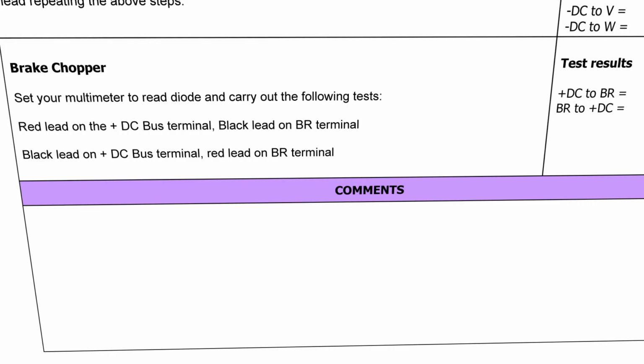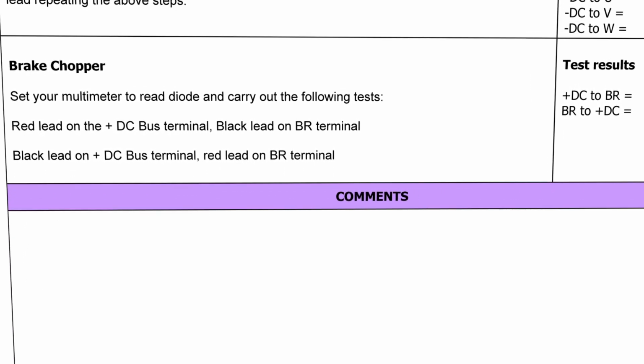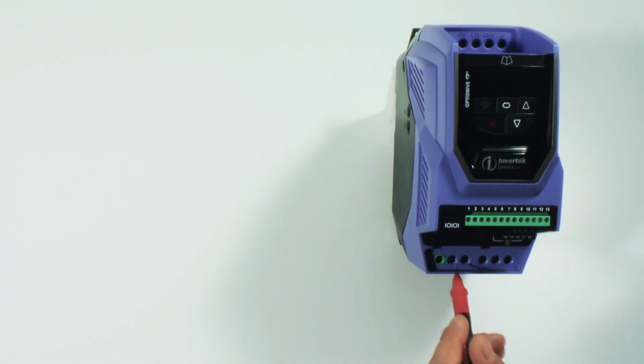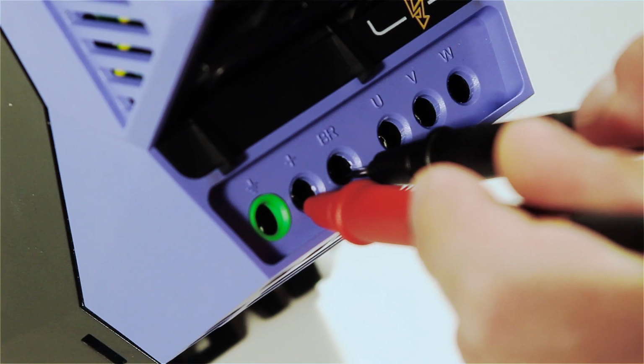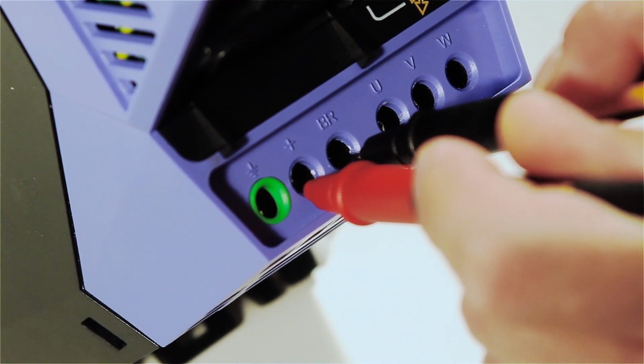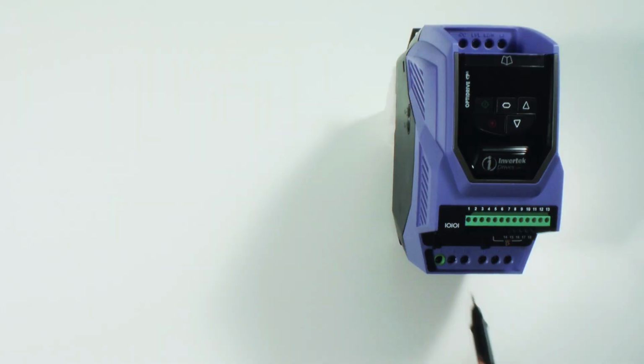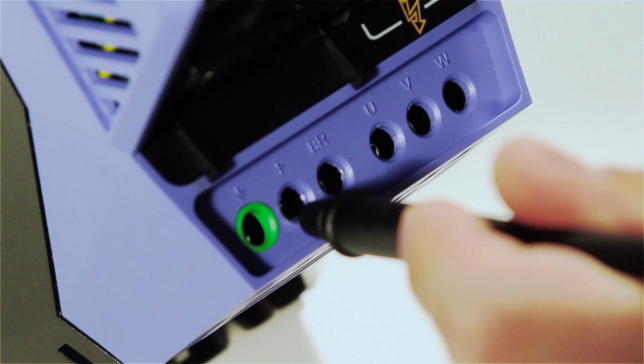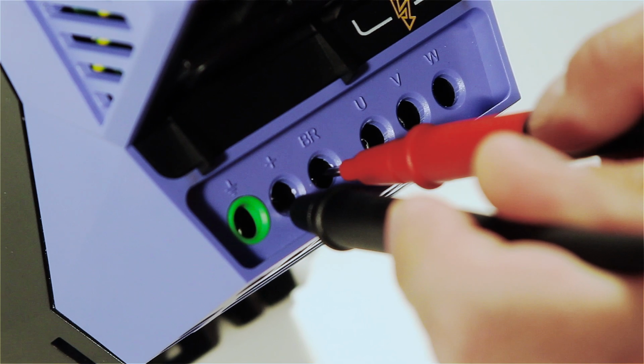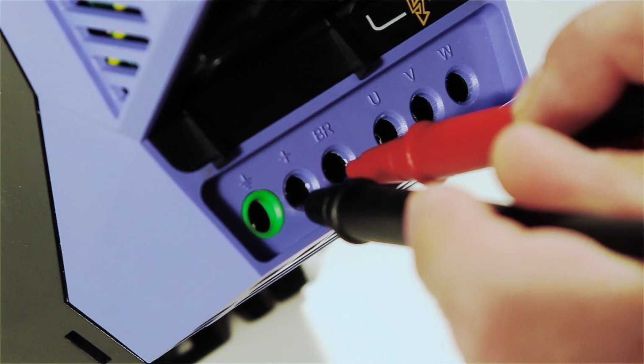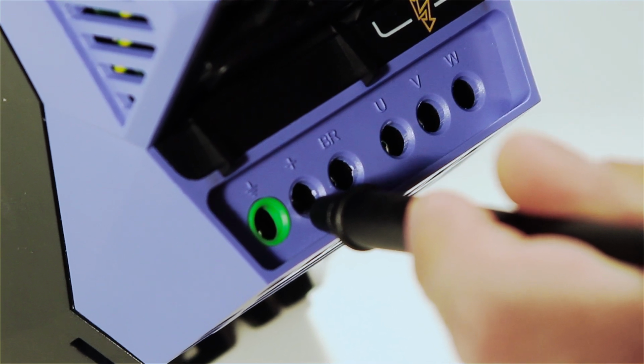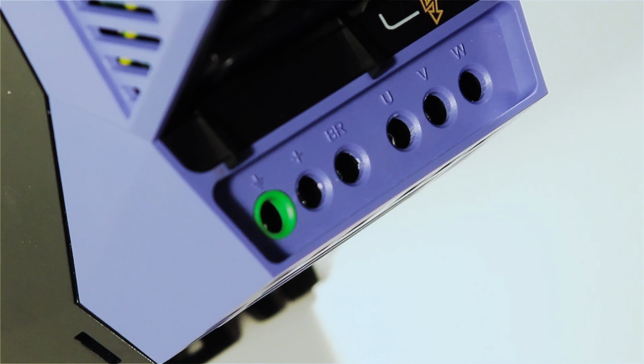The brake chopper circuit. The following tests must be completed. Place the red lead on the plus DC bus terminal and the black lead on the BR terminal. Place the black lead on the plus DC bus terminal and the red lead on the BR terminal. You should now have completed part B of the service request form.